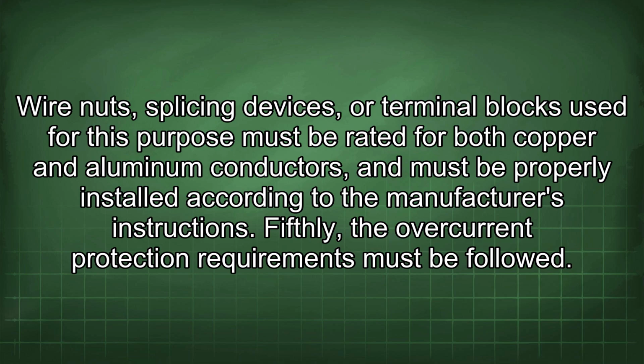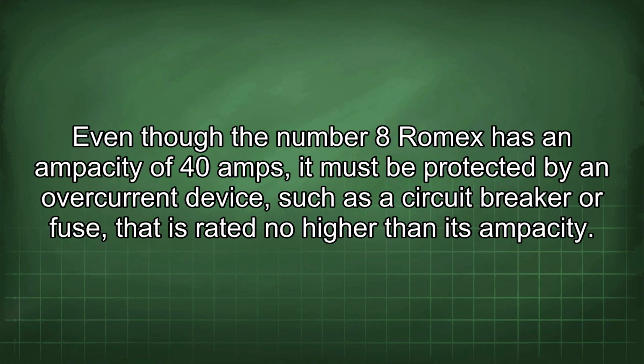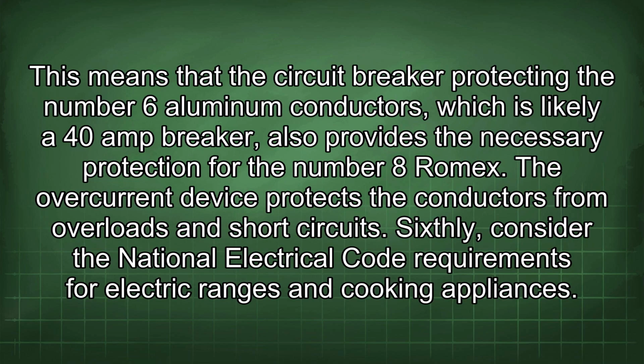Fifthly, the overcurrent protection requirements must be followed. Even though the number 8 Romex has an ampacity of 40 amps, it must be protected by an overcurrent device, such as a circuit breaker or fuse, that is rated no higher than its ampacity. This means that the circuit breaker protecting the number 6 aluminum conductors, which is likely a 40 amp breaker, also provides the necessary protection for the number 8 Romex. The overcurrent device protects the conductors from overloads and short circuits.